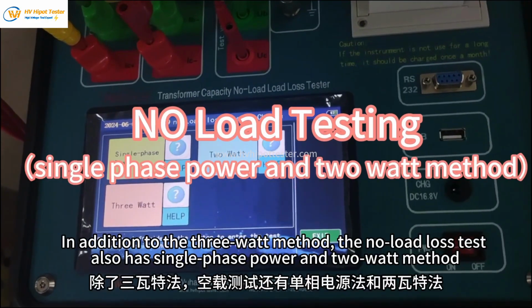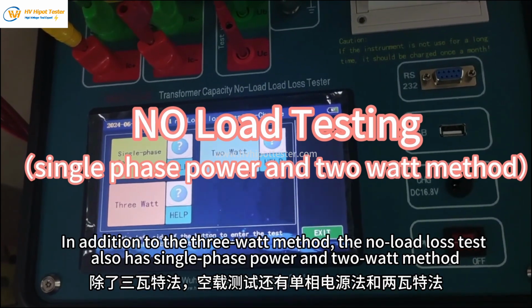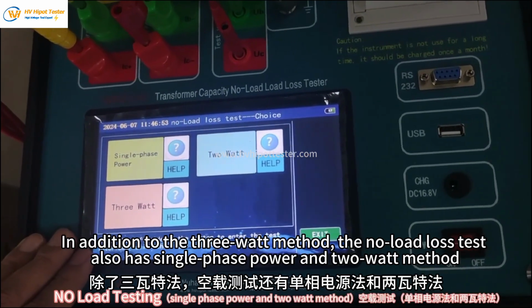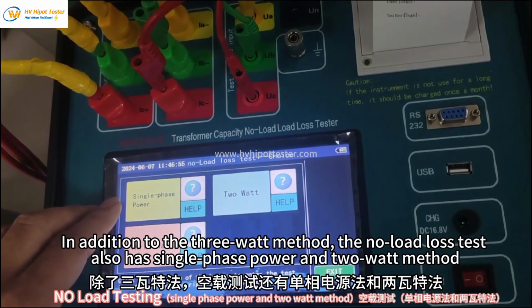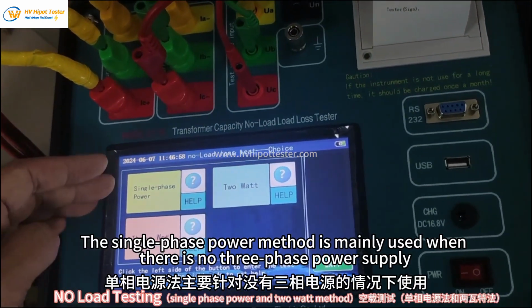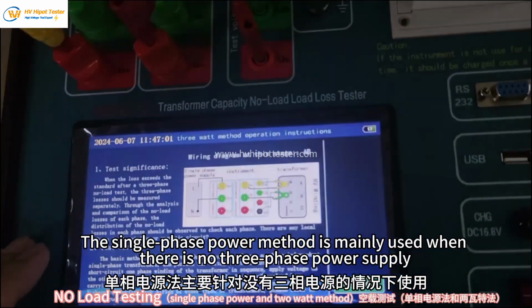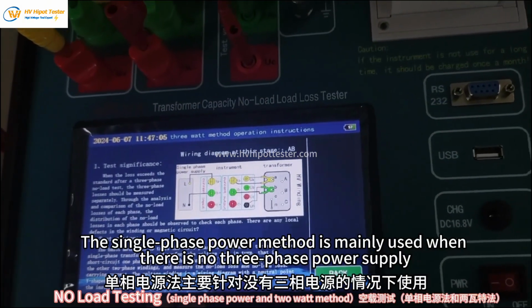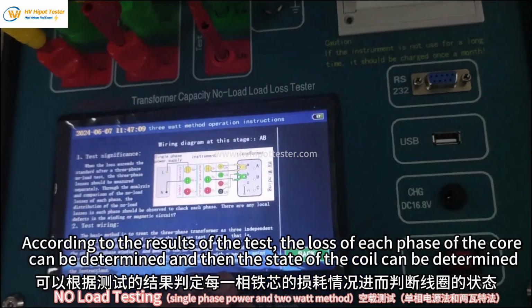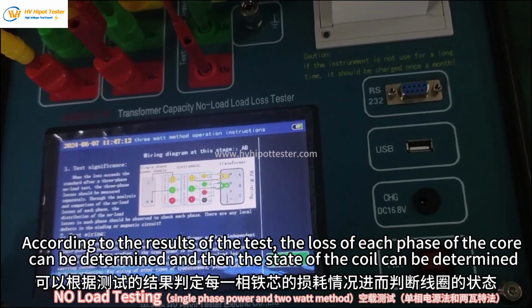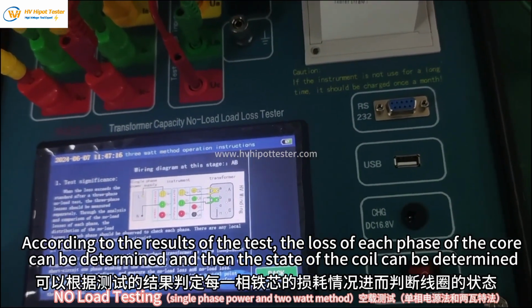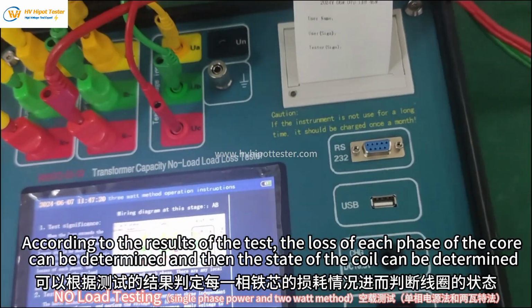In addition to the 3-watt method, the no load loss test also has the single-phase power and 2-watt methods. The single-phase power method is mainly used when there is no 3-phase power supply. According to the results of the test, the loss of each phase of the core can be determined and then the state of the coil can be determined.